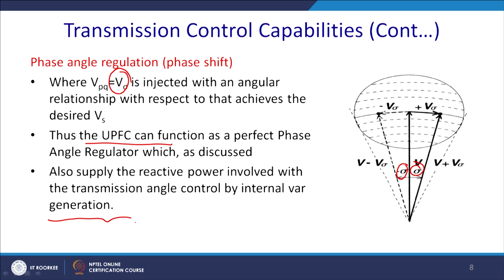Phase angle regulation: it will change the sigma and keep the magnitude the same, where VPQ equal to V sigma is injected with an angle relationship that achieves the desired Vs. Thus, UPFC can function as a perfect phase angle regulator, as discussed here. It also supplies the reactive power involved in transmission line angle control by internal var generation, mainly by this series compensator. So, to optimally use the rating of this UPFC, we may need to take all those parameters into account.